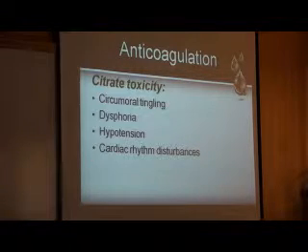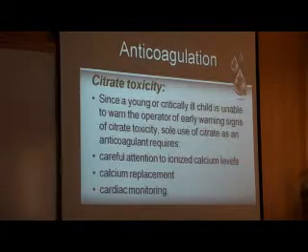We have to be very careful when dealing with a child on an apheresis machine, because citrate toxicity cannot be expressed by the child. He may be unable to say that he has circumoral tingling, and it can advance in a few minutes into life-threatening cardiac arrhythmias and cardiac standstill. So the child cannot express himself. I have to search for the toxicity. I have to monitor the child, measure ionized calcium before and after the procedure, and keep an eye on him.